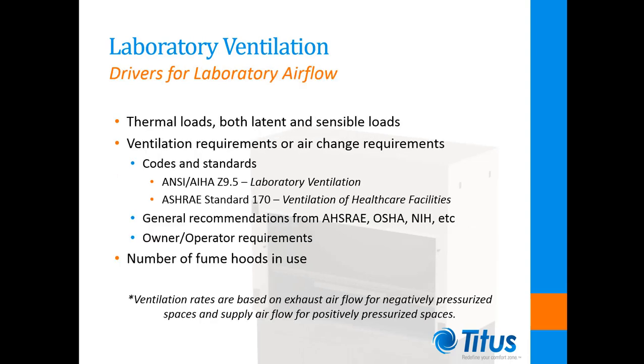Determining the airflow rates for laboratories begins with looking at the thermal loads in the space. At a minimum, we need to supply enough air to maintain space temperature and humidity within the desired range. Independent of thermal comfort requirements, the minimum air change rate needs to be established next. The most widely used reference is ANSI standard Z9.5, a laboratory ventilation standard established by the American Industrial Hygiene Association. It recognizes that ventilation is a tool to control exposure to contaminants, but should not be solely relied upon as a means of removal, as it is generally ineffective. Instead, contaminants should be controlled at the source of generation, for example, within a fume hood.